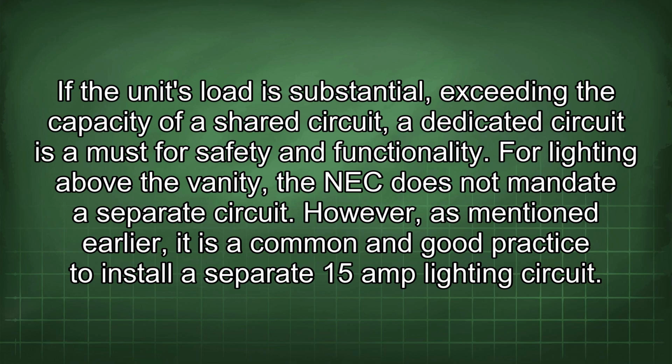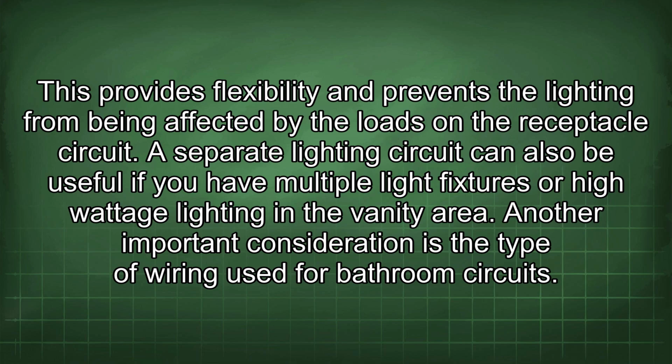For lighting above the vanity, the NEC does not mandate a separate circuit. However, as mentioned earlier, it is a common and good practice to install a separate 15-amp lighting circuit. This provides flexibility and prevents the lighting from being affected by the loads on the receptacle circuit. A separate lighting circuit can also be useful if you have multiple light fixtures or high wattage lighting in the vanity area.